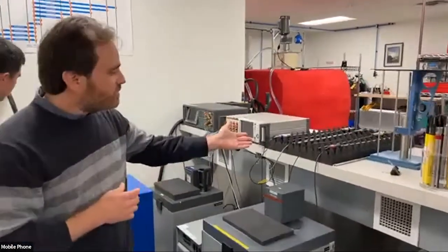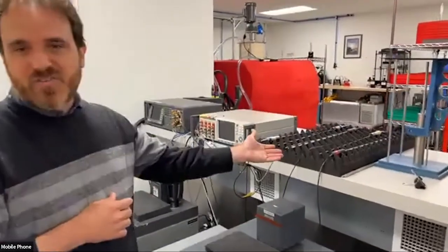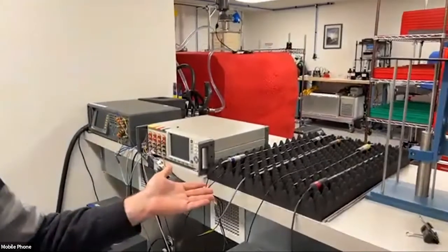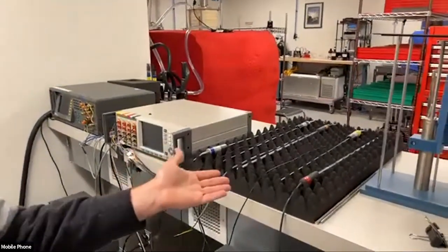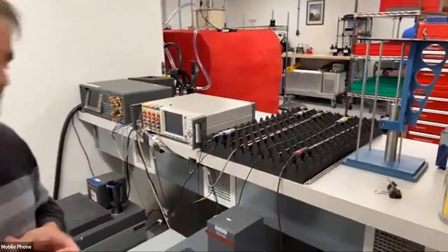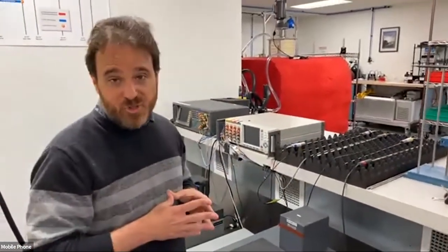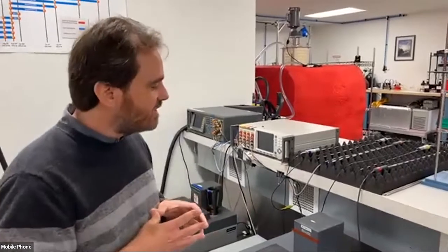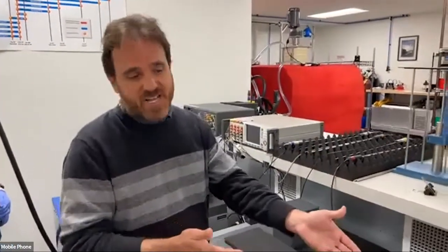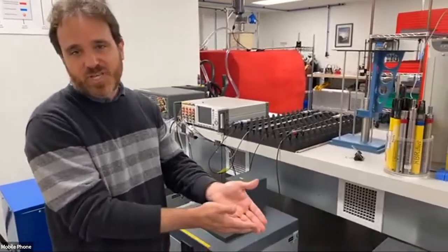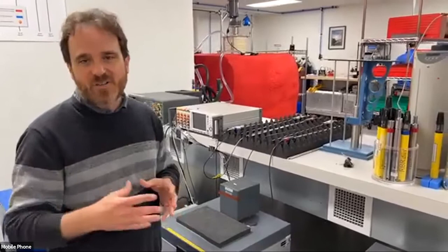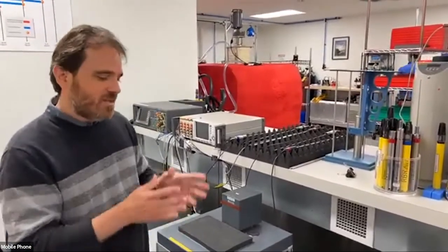The reference standard that we use is an SPRT, or a standard platinum resistance thermometer. We have 2 models right now, but mostly we use our Isotech 670 SL models, which are metal sheathed SPRTs. The way it works is we introduce our reference standard as close as possible to the marine thermistor, and then we start the 8-point cycle that I just spoke about.